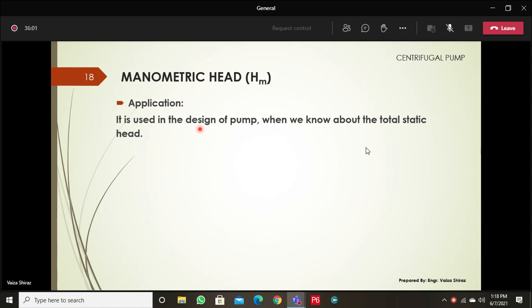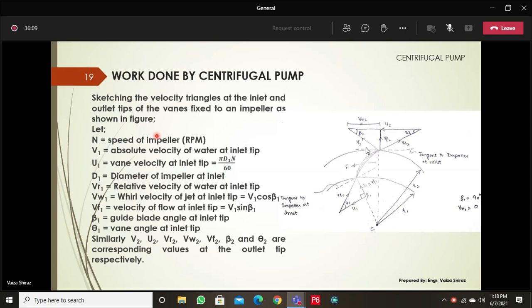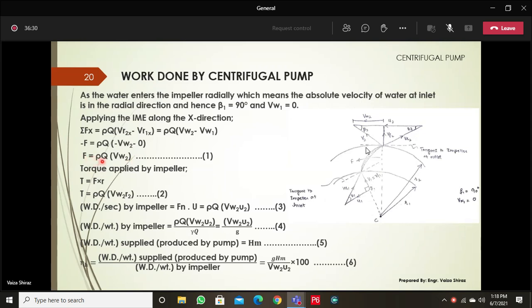The manometric head is used in the design of the pump. For the work done by the centrifugal pump, you draw velocity triangles at the inlet and outlet tips of the impeller blades. The work done per second by the impeller — which is the input energy — is different from the work done on the water delivered by the pump, which is the output. Their ratio gives the hydraulic efficiency.